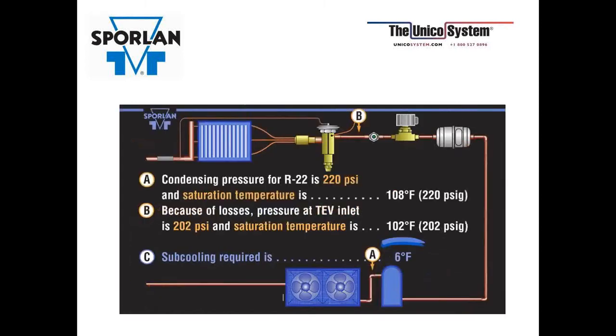So the condensing pressure at point A is 220 psi, which is a saturated temperature of 108. And because of those losses, you lost 18 psi. By the time it gets to the inlet of the TEV, it's 202 pounds of pressure, which is equal to 102 degrees on the PT chart. So that tells you that you need at least 6 degrees of subcooling from point A to point B to make sure you still have a full column of liquid at that point.